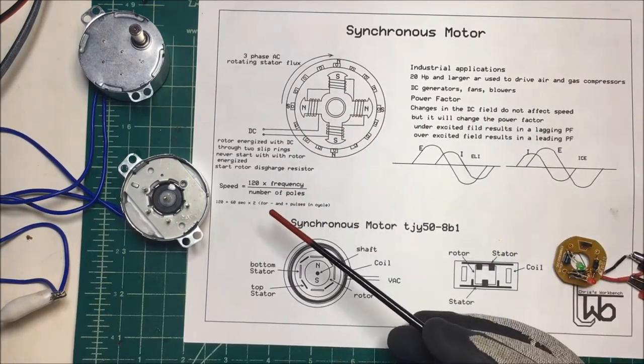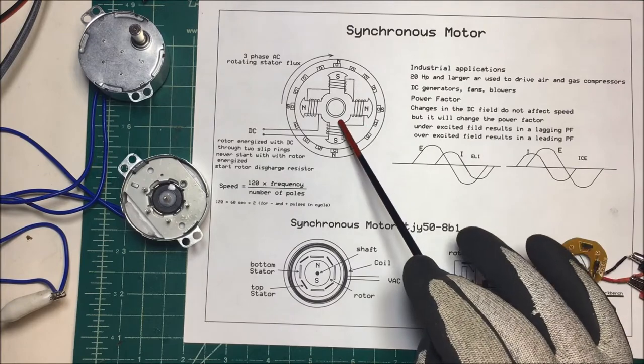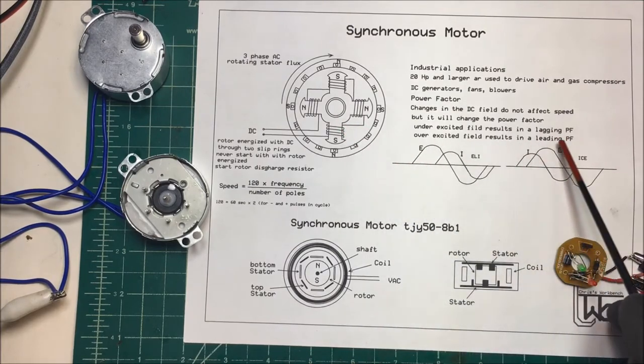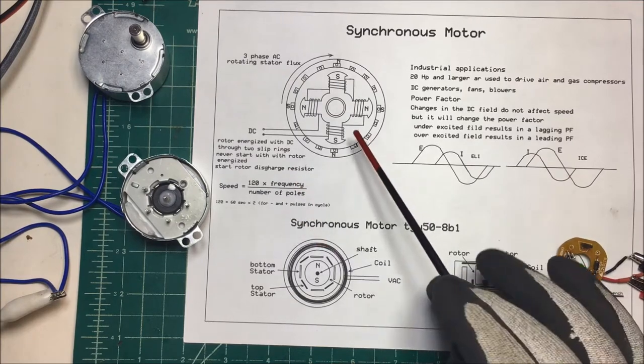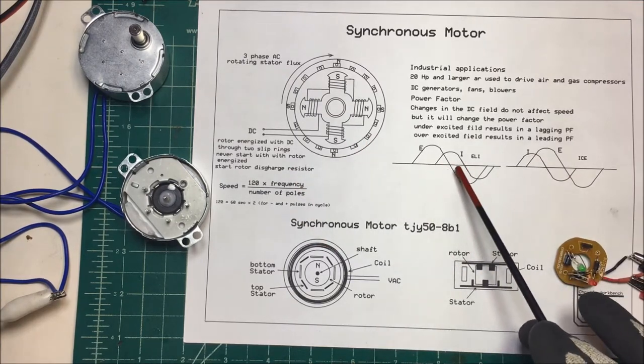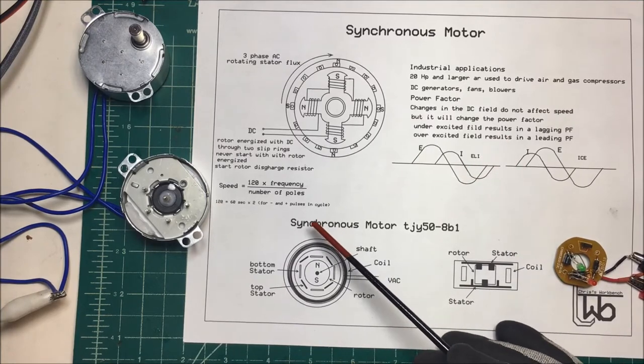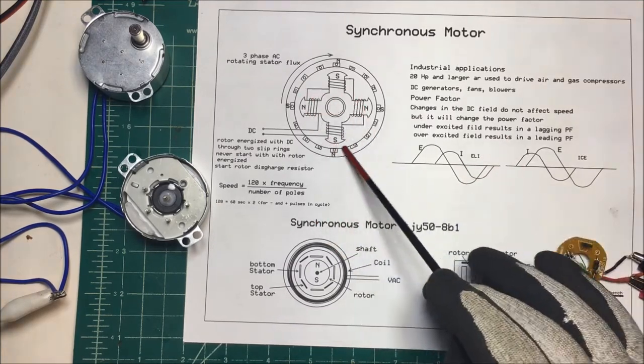If you under excite this field, it results in a lagging power factor. And if you over excite it, you have a leading power factor. So if you have a lot of inductive load in your building, then you can correct the power factor.